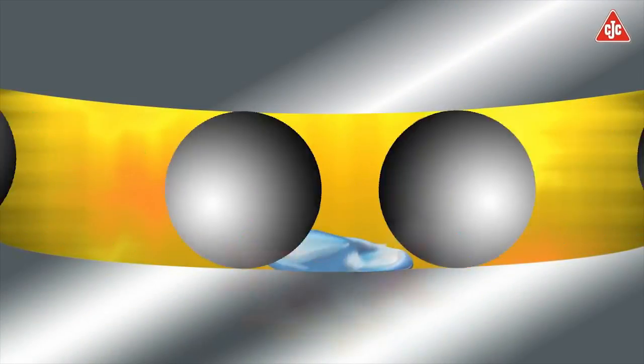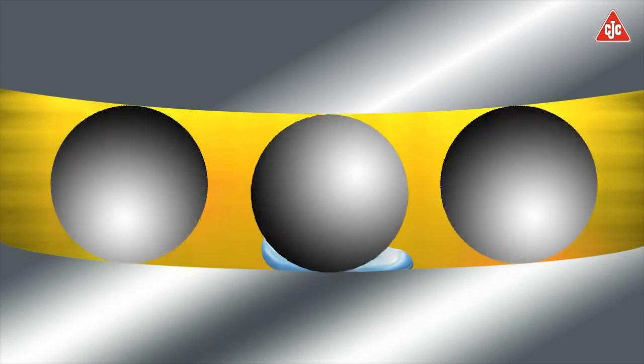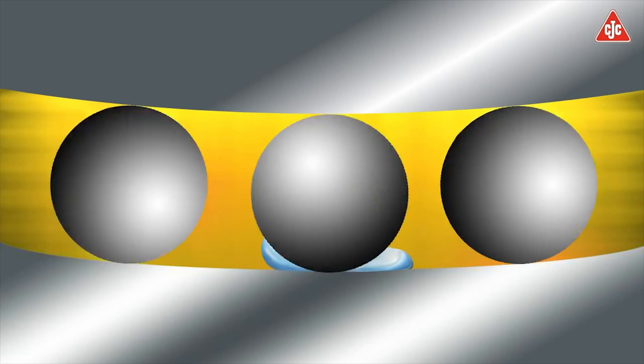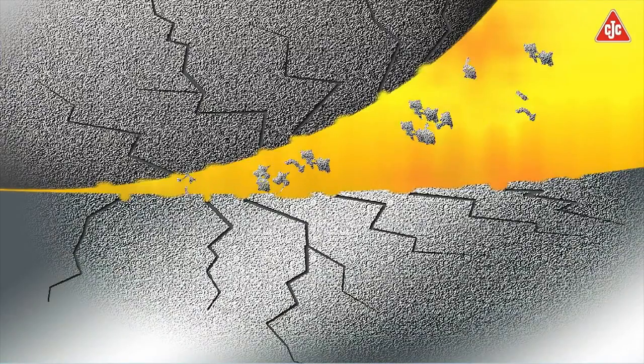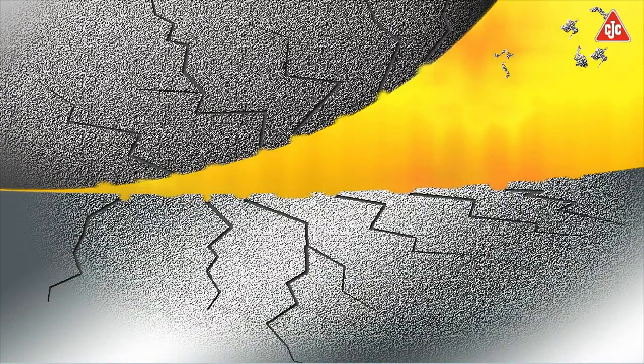Even small amounts of water reduce the lubricity of the oil. When water is exposed to high pressure, found for example in bearings and gears, water droplets collapse. This results in micro-pitting in metal surfaces.